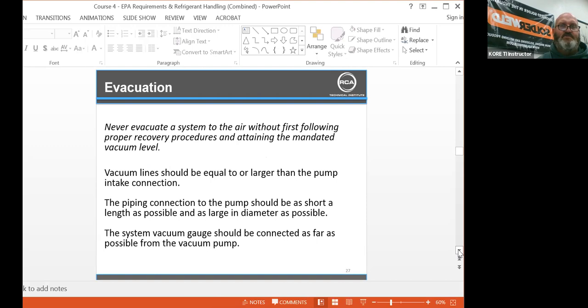Never evacuate a system to the air without first following proper recovery procedures, attaining the mandated vacuum level. Vacuum lines should be equal to or larger than the pump intake connection. Most guys, even though there was just a poll done on social media that said 61% of the techs polled are still running their vacuum through their manifolds, a lot of guys are switching over to a charging tree. They're building a charging tree and running it not through the manifolds, but through pipe connections. They're seeing faster recovery and evacuation times.